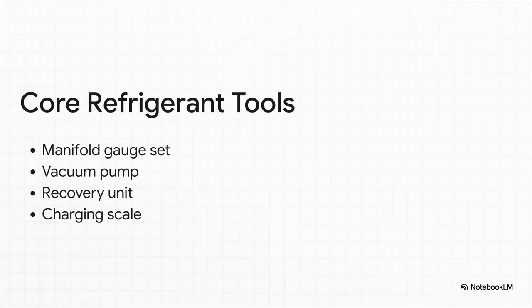The core of your setup really comes down to a few non-negotiables: a professional-grade manifold gauge set, a powerful vacuum pump for moisture removal, a dedicated refrigerant recovery unit, and a precise charging scale. Notice I said professional grade. Entry-level gear just breaks down. These tools must be perfectly compatible with the specific refrigerant you're working with, especially flammables, to ensure accurate charging and a safe, deep evacuation of the system.